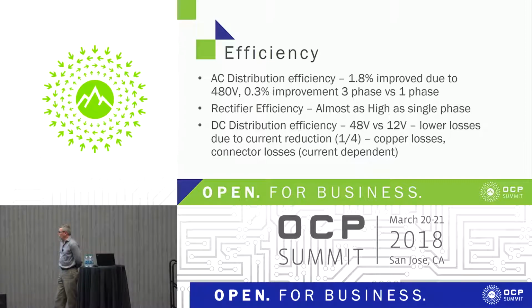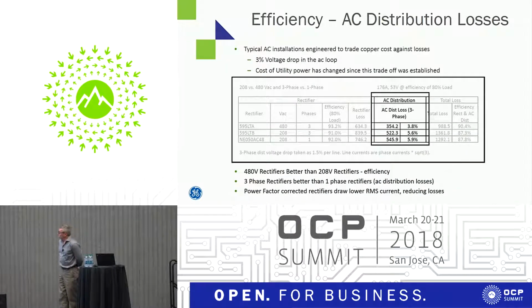But we still achieve 97-point-something% efficiency in the actual rectifier itself. And then the DC distribution efficiency, obviously 48 volt. If you compare it with 12 volt, the losses are lower, and the ease of providing battery backup is improved as well. We did some studies a while back on where that AC distribution loss occurs, and compared for different rectifier styles in terms of the 3-phase 480 volt, the 3-phase 208 volt, and a single-phase 208 volts, and you can see that there's a considerable improvement in distribution efficiency. The losses are significantly lower in a 3-phase distribution system.